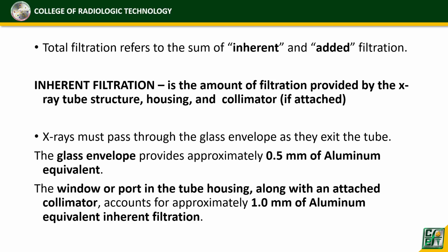The window and port of the tube housing, along with an attached collimator, account for approximately 1.0 millimeter of aluminum equivalent inherent filtration.